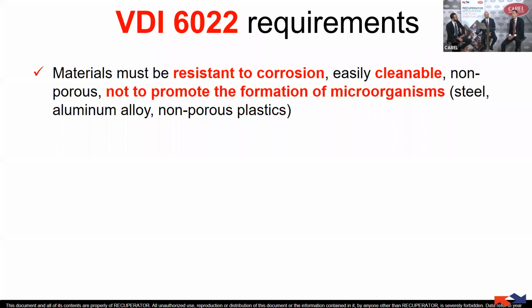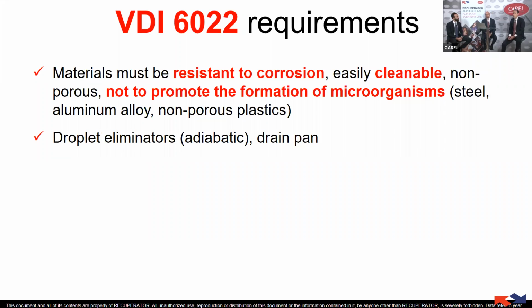The humidifier for the hygienic application has to be made of a material that is resistant to corrosion, easy to clean, and does not promote the formation of microorganisms. Typical materials we can use are stainless steel, for example, or aluminium. VDI 6022 also gives you requirements about the drainage of non-evaporated water.